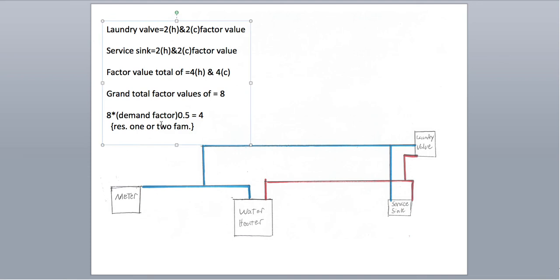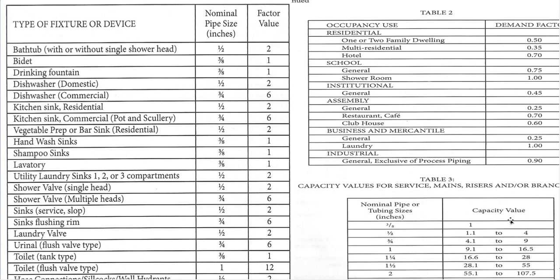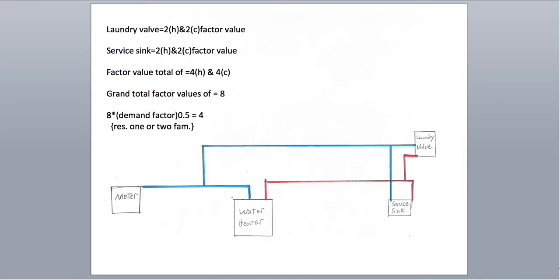Now you take that four and go back to the capacity values — 1.1 to four is half-inch. Three-eighths is too small, obviously. But keep in mind your smallest water main is three-quarter inch. This right here is just a branch, just a section of your water pipe — that's just for example. But if you had a whole house, you just go around. If you take it by section it's a lot easier. Do your sections, then follow your branches and risers and break it down that way. If you take your time, it's just as simple as doing this.